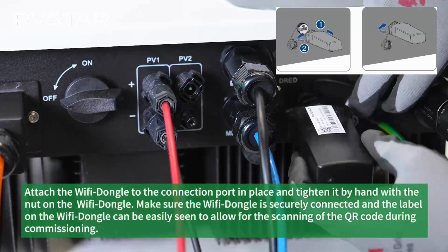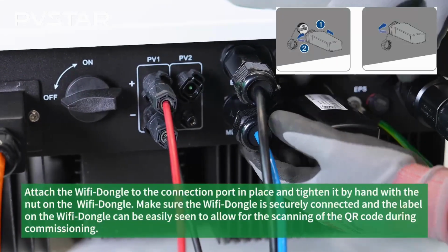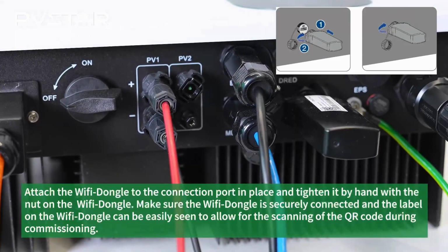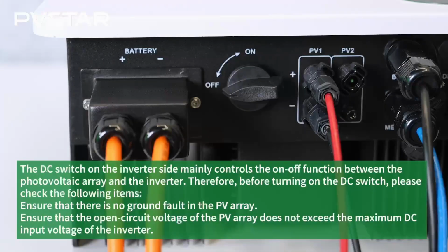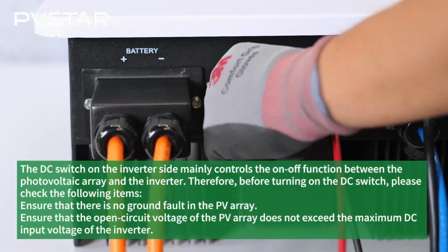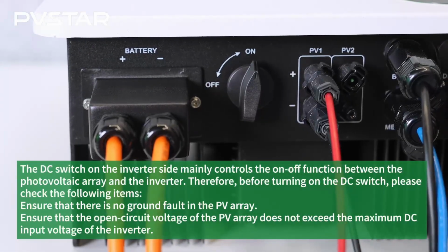Attach the Wi-Fi dongle to the connection port in place, and tighten it by hand with the nut on the Wi-Fi dongle. Make sure the Wi-Fi dongle is securely connected, and the label on the Wi-Fi dongle can be easily seen to allow for the scanning of the QR code during commissioning. The DC switch on the inverter side mainly controls the on-off function between the photovoltaic array and the inverter. Therefore, before turning on the DC switch, please check the following items. Ensure that there is no ground fault in the PV array. Ensure that the open circuit voltage of the PV array does not exceed the maximum DC input voltage of the inverter.